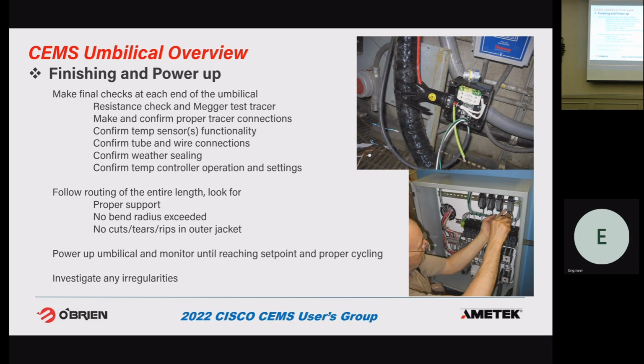So check all these things. Then check if you have a temperature controller and confirm it's working correctly. Check your supply voltages and all that. Make sure you've got proper support and that bend radiuses are not exceeded. Then power it up, set all the parameters on your controller, watch it hit temperature and turn off, make sure it cycles through at least a couple cycles, and monitor it.